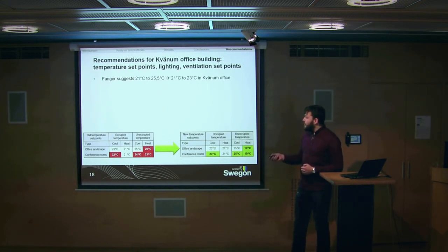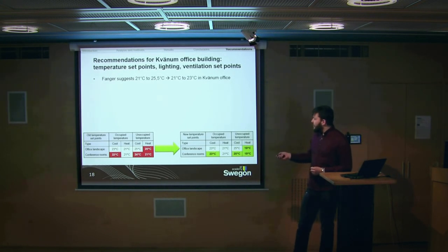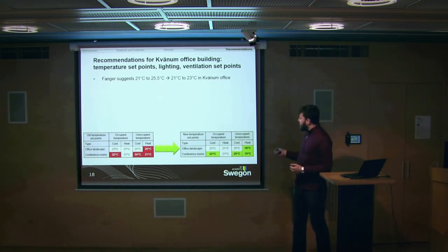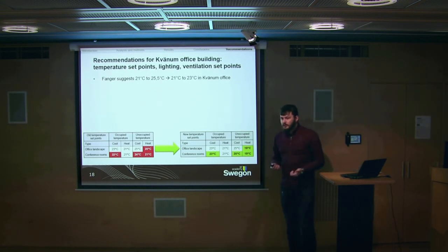So all the heating and cooling set points for when the room is occupied are the same, and before they were different. So the cooling set point is 23 degrees Celsius, and the heating set point is 21 degrees Celsius when the room is occupied. And when it's unoccupied, the cooling goes to 25 degrees Celsius, and heating goes to 19 degrees Celsius. So there's a difference of 2 degrees Celsius in each case. It's interesting that the PMV-PPD model from Fanger suggests 21 degrees to 25.5 degrees to use as set points for the indoor temperature, but it proved to be that 21 to 23 degrees Celsius was the best for the Kvänum office.